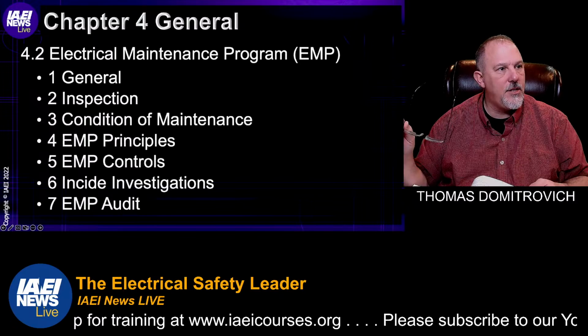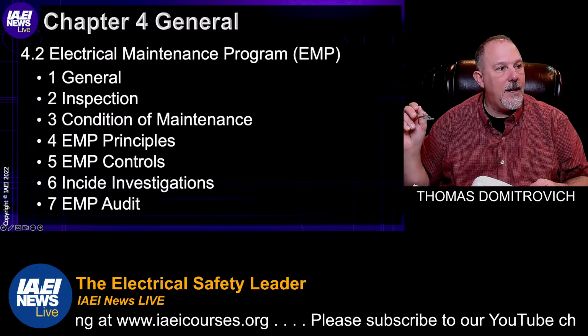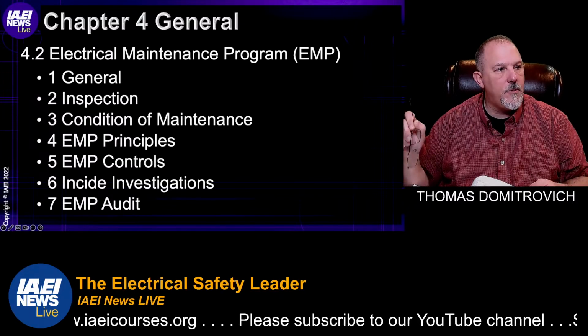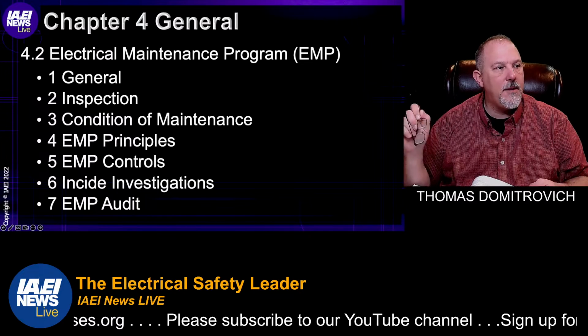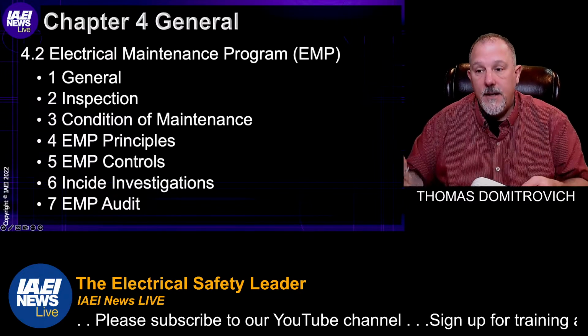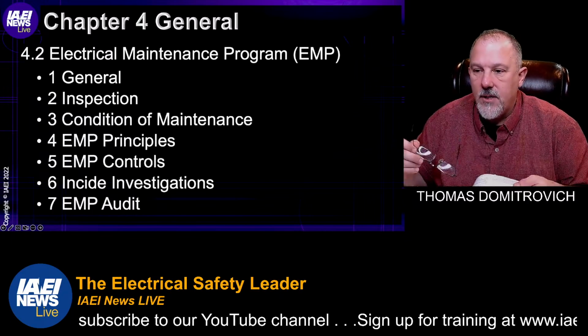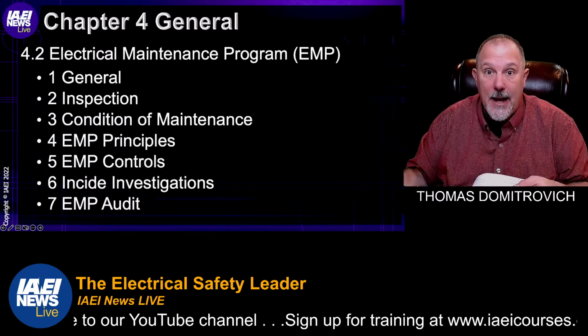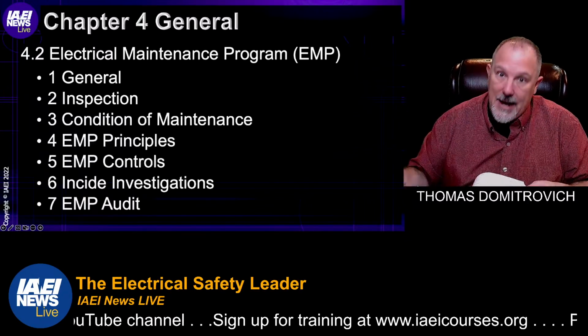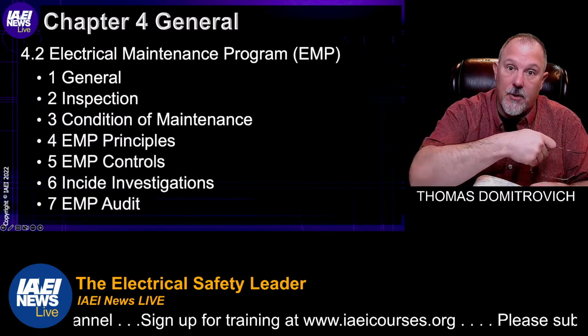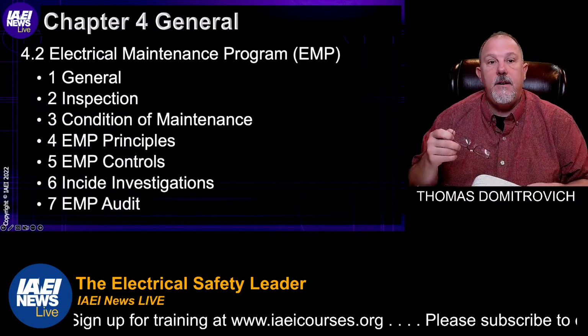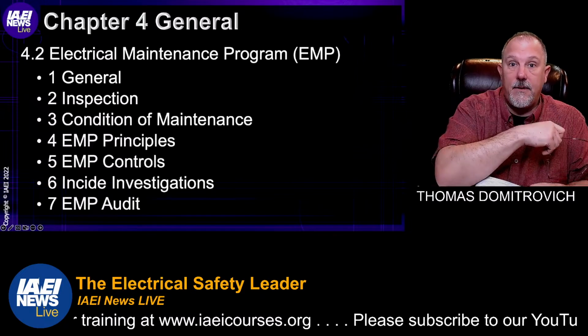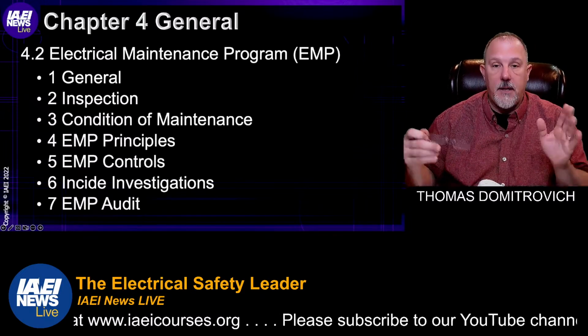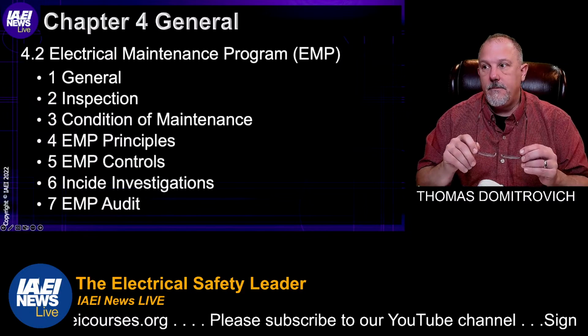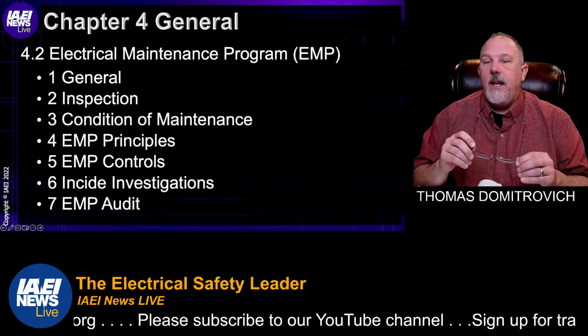It just says verify the electrical equipment or systems have been inspected to comply with the applicable codes. So if the panelboard is not rated for the conditions, then it would not comply with the NEC installation requirements, and then bam, then you have a problem. You have to fix that. Because maintaining something, I guess here's the point, Willie.